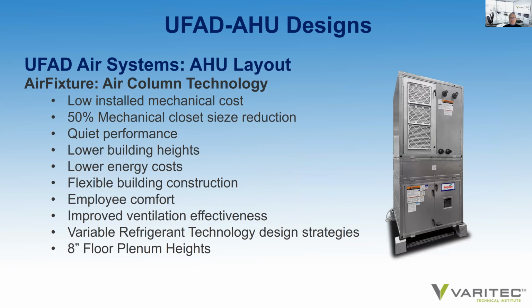However, there's a newer technology today, and Airfixture has certainly advocated for it and actually manufactures this device. It's called an air column. Air columns are mounted in the building itself in mechanical closets. These mechanical closets are potentially 50% smaller than you might see in a medium pressure VAV indoor air handler application. They're very quiet. They allow for lower building heights. You don't have a lot of mechanical equipment on the roof of a building.